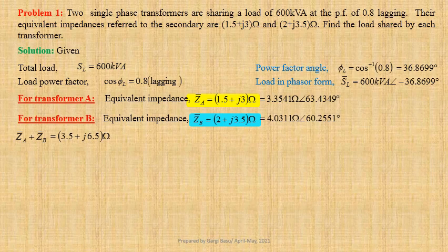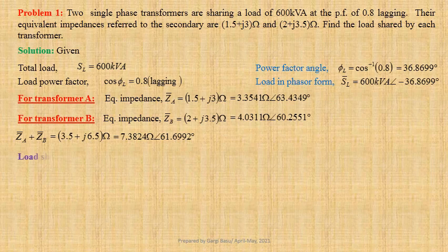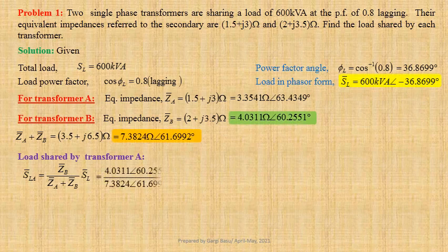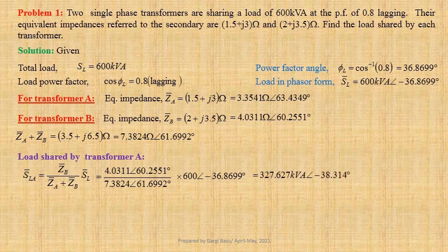This may be written in polar form as 7.3824 ohm at an angle 61.6992 degree. Load shared by transformer A, SLA equals ZB divided by ZA plus ZB into SL. Using values, we get 4.0311 at an angle 60.2551 degree divided by 7.3824 at an angle 61.6992 degree into 600 at an angle minus 36.8699 degree.